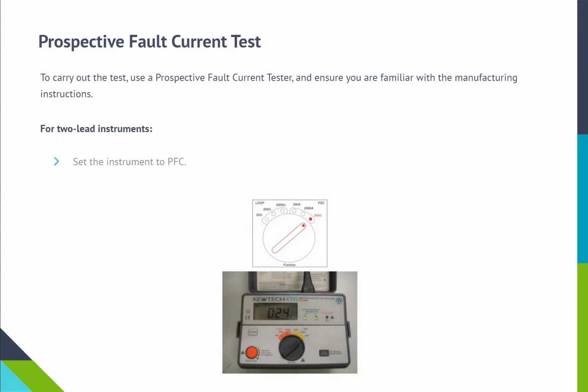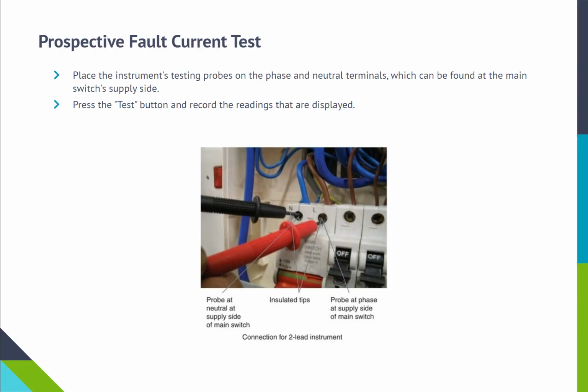To carry out the test, use a prospective fault current tester and ensure you are familiar with the manufacturer's instructions. For 2 lead instruments, set the instrument to PFC. Place the instrument's testing probes on the phase and neutral terminals, which can be found at the main switch's supply side. Press the test button and record the readings that are displayed.